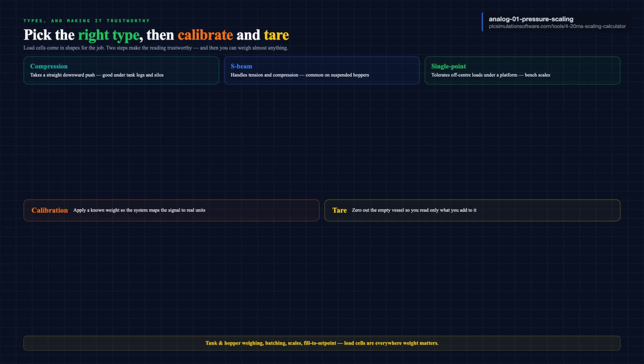Whatever the type, 2 steps make it trustworthy. Calibration. You tell the system a known weight, so it maps the signal to real units. And tare. You zero out the weight of the empty vessel, so you read only what you add. Get those right, and you can batch ingredients, weigh a silo, or fill to a set point, all from a number your PLC trusts. Tanks, hoppers, scales, batching lines. Load cells are everywhere weight matters.